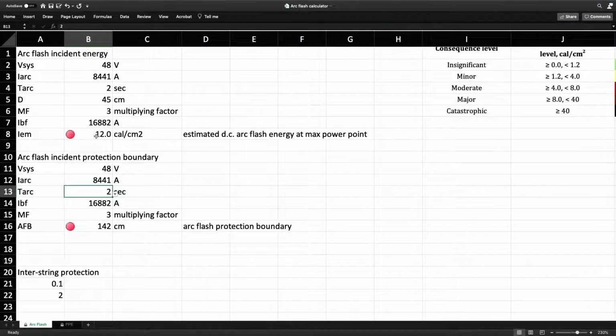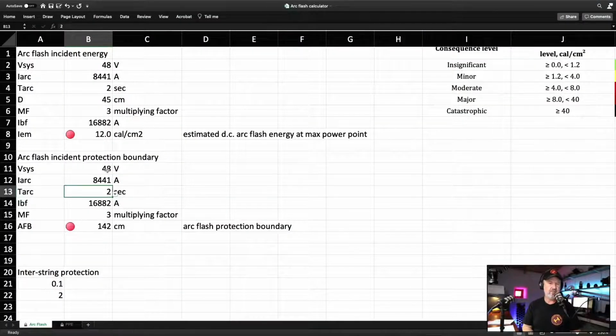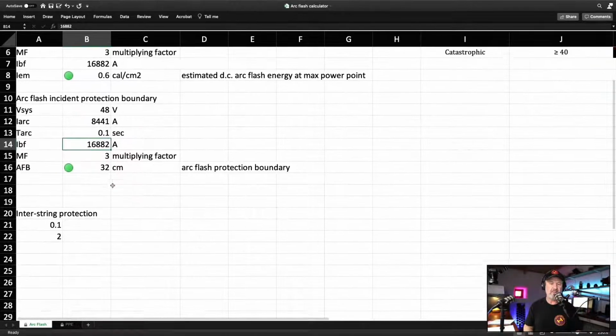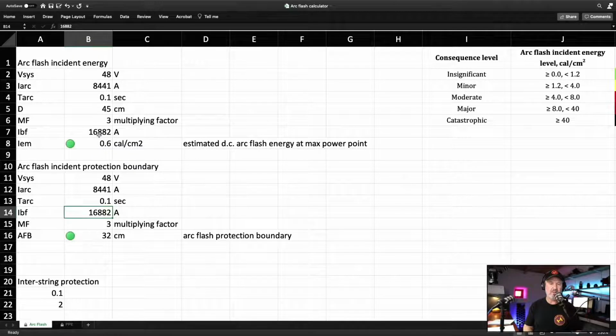So going back to my calculator now, here we go. If we're doing a bus bar fault, we've now got 48 volts, yes, but we have interstring overcurrent protection, which means we can drop our arcing time right down. So I'll drop our arcing time down to 0.1, and our bolted fault current now is no longer 16,882 amps, because we've got interstring overcurrent protection. Now, in this case, we might have put in some 250 amp fuses, so we find out what their trip time is. Let's just imagine that in 0.1 of a second they get up to 400 amps.